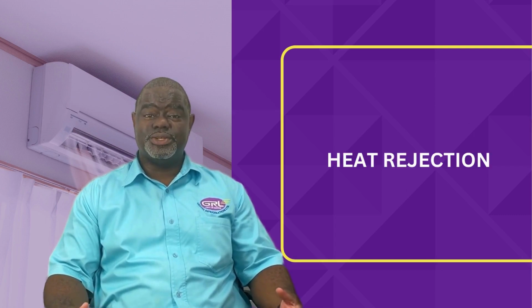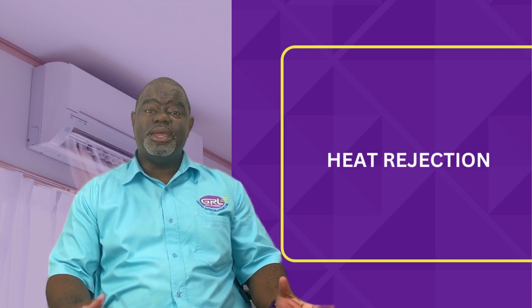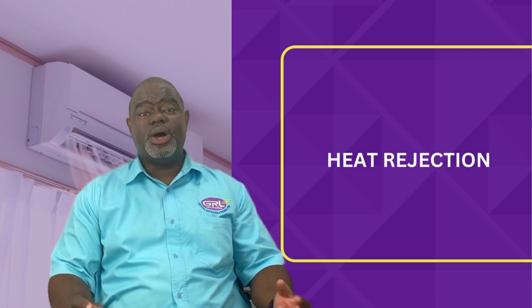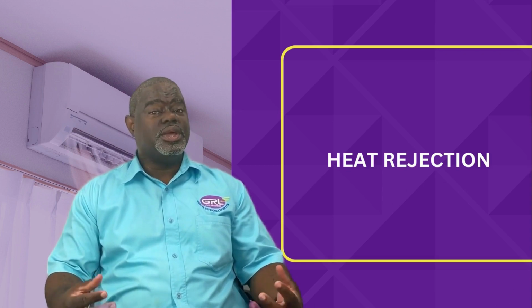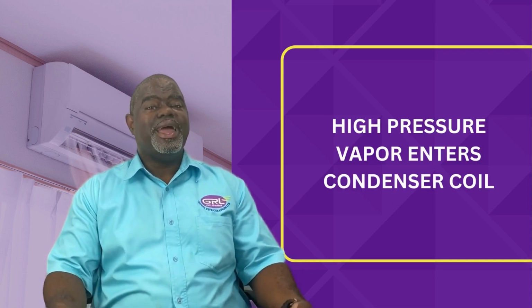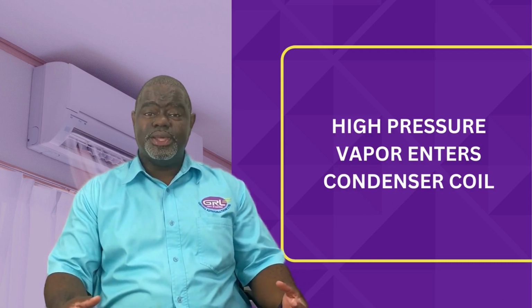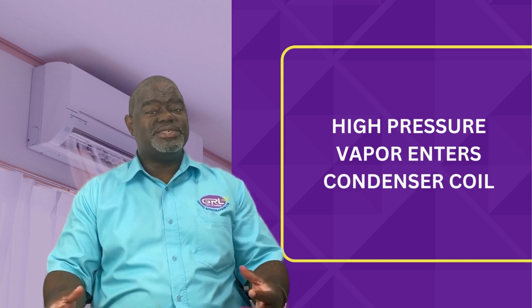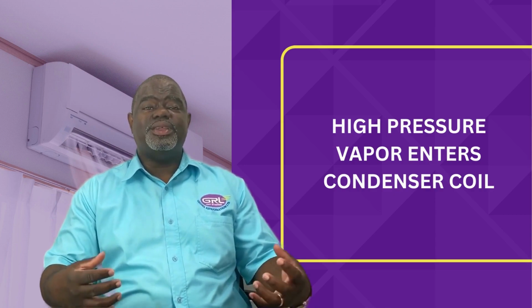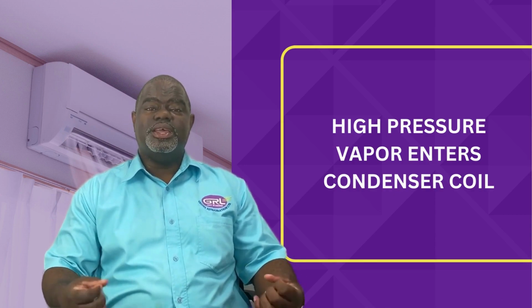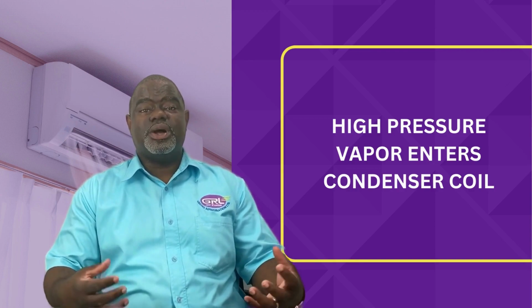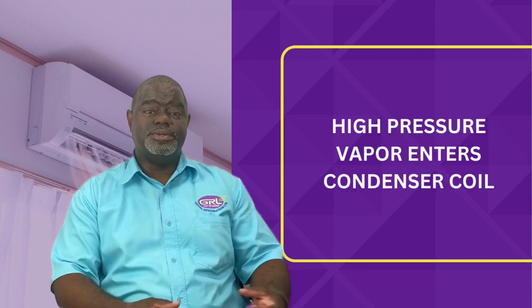The condensing coil in an HVAC system is responsible for heat rejection. The heat that is absorbed from inside the building is rejected to outside through the condenser coil. This happens when the high temperature, high pressure vapor enters into the condenser coil and is cooled by air passing over the coil, thereby condensing into a liquid, giving up the heat which it collected from inside the building.